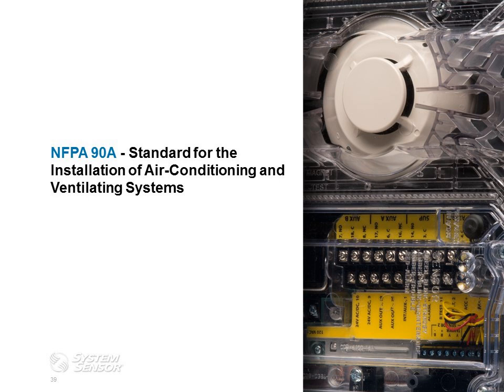So that's what the International Mechanical Code states. That's their standard. Now, NFPA 90A, a standard for the installation of air conditioning and ventilating systems, is very similar in scope and requirement to the International Mechanical Code. The main difference is that NFPA 90A states that placement of the duct detectors will be on the supply side versus the return side.